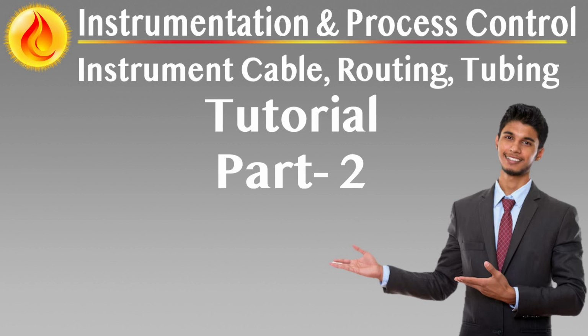achieve logical marshalling. Thermocouple circuits require extension cabling all the way to the point of cold junction compensation, typically the input card of the receiving device. The correct polarity and cable type must be maintained throughout the run. Instrument cabinets must be configured to accommodate full signal capacity, including designated spare channels. Modular system cabling between instrument cabinets and MDFs ensures standardized terminations and minimizes installation errors. The instrument cabinet design must reserve at least 20% spare I/O capacity for operational flexibility and future expansion.